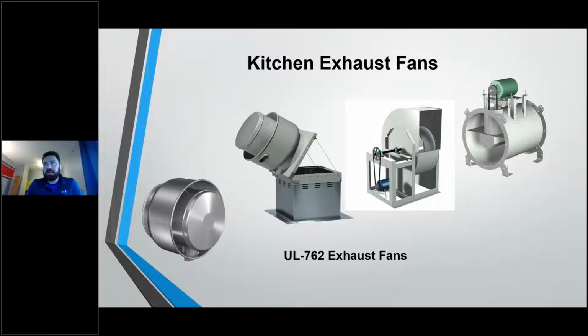One commonly missed item in specification of upblast grease exhaust fans is that people don't take into account the insulation thickness on the roof. So they may say, oh, this is a 40-inch tall curb, or a 24-inch tall curb with a 16-inch wind band to get me to 40 inches. But they'll forget that, hey, that roof deck has 2, 3, 4, 5 inches of insulation in there. So now this wind band is not 40 inches above that finished roof deck.